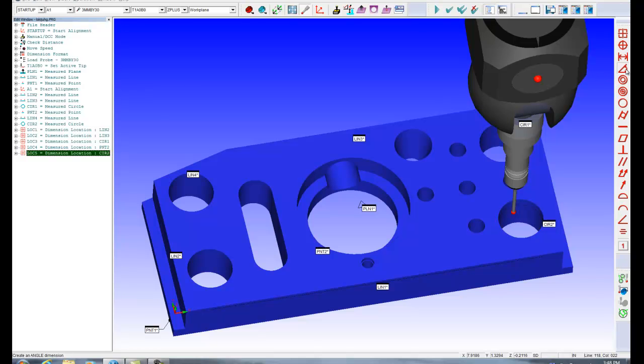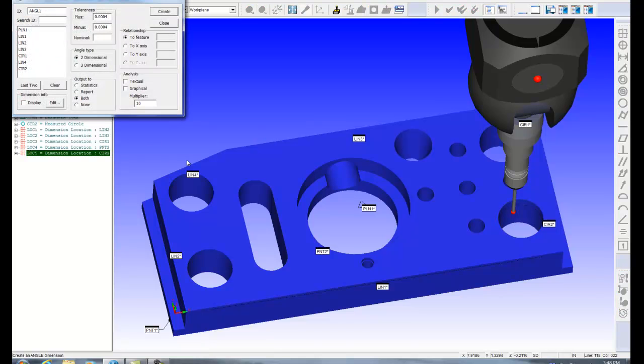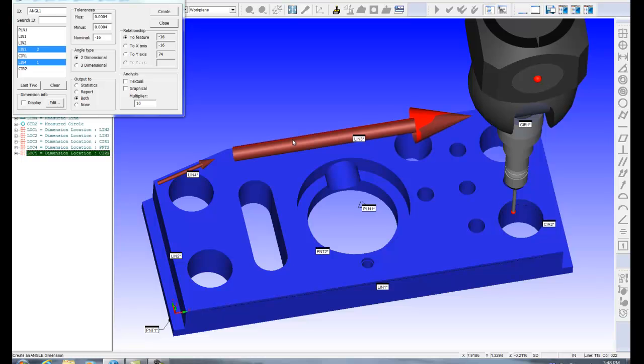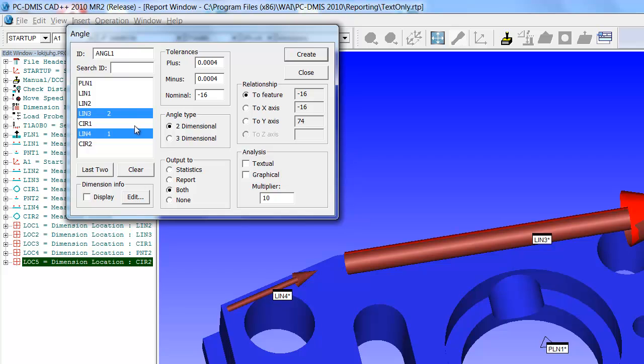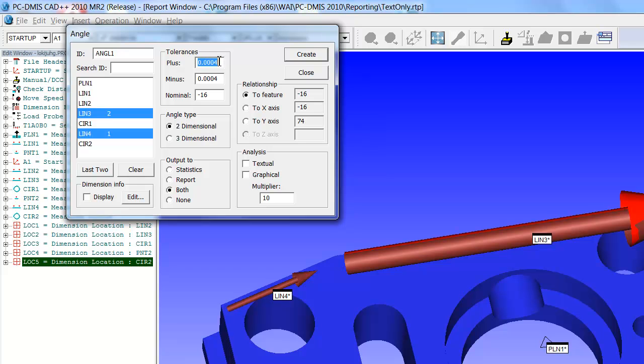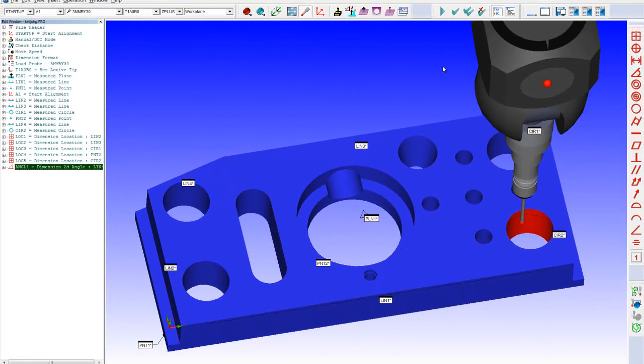I want to go do some other dimensions. Let's say I want the angle between this feature and this feature. This is one of the really nice features of this software. Again, you're going to be measuring lots of features, and this list over here in this angle menu is going to be pretty long, potentially. So, to have to scroll through that window to find the feature names that you want can be time consuming. So, you don't have to do that with PCDMIS. Again, you just click on the screen where the features are and it selects them for you. In this case, I want to change the tolerance to plus or minus a degree. Say go and it just added that to my report.